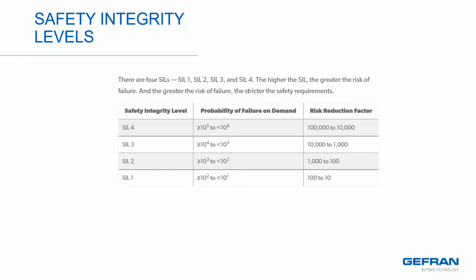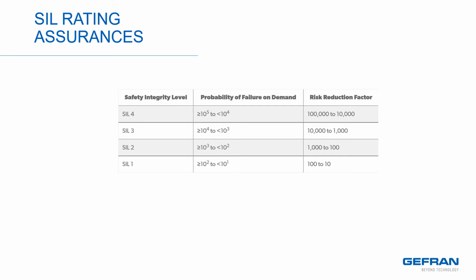SIL, or safety integrity levels, are determined by identifying hazards and assessing their risk. There is no method or scoring system. Rather, a producer or user will simply use their own data to determine an acceptable level of risk mitigation they wish to apply. Gefran produces products with a SIL2 rating, which is becoming more commonly demanded in industrial applications, as well as OEM designs for mobile hydraulics. It illustrates how different levels of safety integrity level rating allow for assumptions about reliability and outcomes.